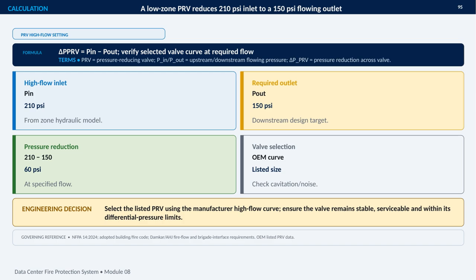I also need to verify the manufacturer's listed high flow curve at the required flow, using the correct valve size and configuration. The selection must remain stable and serviceable, while staying within the valve's differential pressure limits. I should also check for potential cavitation and excessive noise, since both can affect reliability and maintenance. The engineering decision, then, is to select the listed PRV based on the OEM high flow data, and confirm that it satisfies the system's hydraulic requirements and applicable governing references, including NFPA 14, the adopted fire code, and AHJ or Brigade Interface requirements.